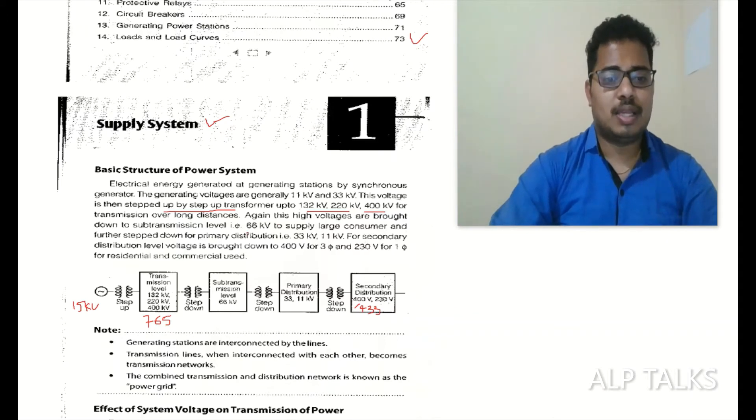These high voltages are brought down to sub-transmission level, that is 66 kV, to supply large consumers and further stepped down to primary distribution, that is 33 kV to 11 kV. For secondary distribution, level voltage is brought down to 400 volts for three phase and 230 volts for single phase for residential and commercial usage.